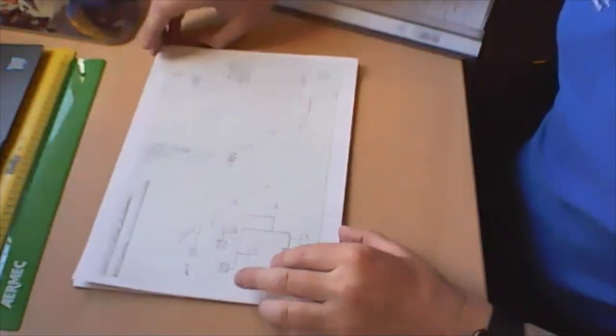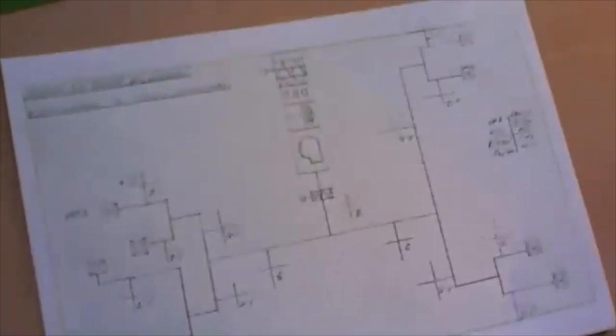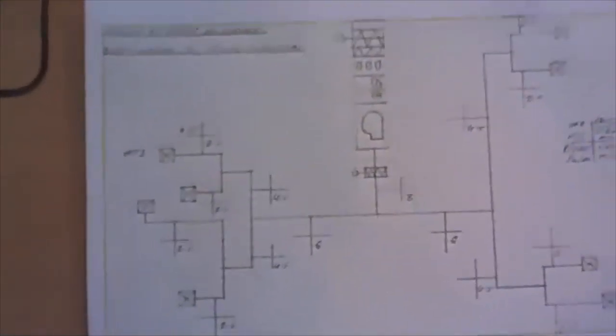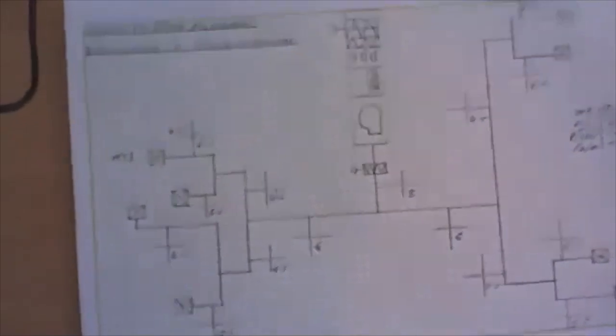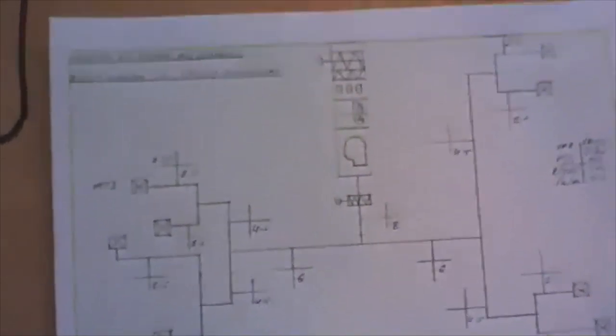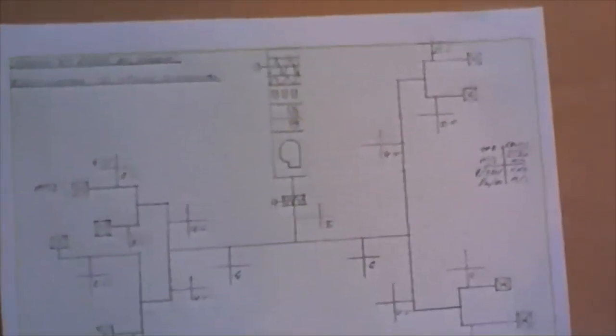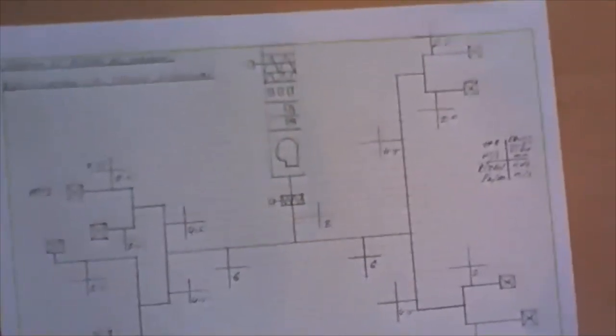I'll show you a drawing here — I have another camera just set up on the side. This is an arrangement where we have a number of diffusers strategically placed. You need to be conscious of diffuser sizing and spacing and ensuring that the air velocity coming down to people isn't very high, or you'll get drafts and uncomfortable environments — especially in an office where people are sitting. As you can see, we've strategically laid out our diffusers, and these are going to toilets.